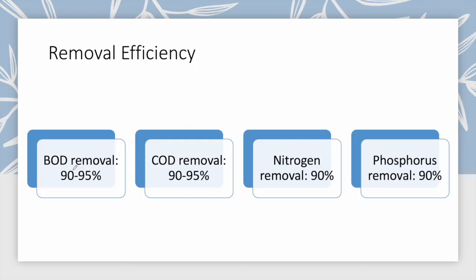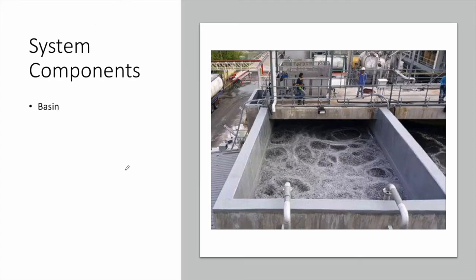A properly designed MBBR wastewater treatment plant can achieve very high removal efficiencies: up to 95% for BOD, up to 95% for COD, up to 90% for nitrogen, and up to 90% for phosphorus.